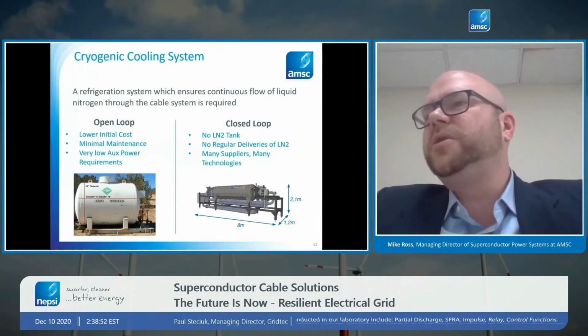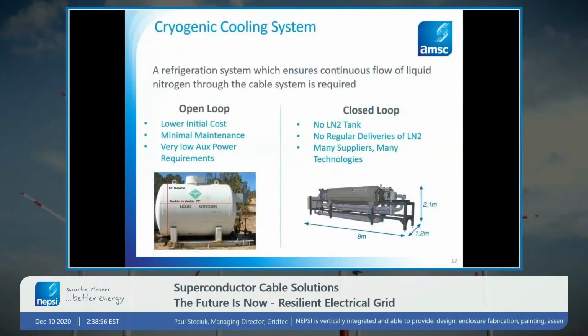Cooling systems are another really important part of these projects. So we talked a little bit about how we have to keep the cables cold. So there's two main technologies. There's open loop cooling systems and closed loop cooling systems. Open loop is usually more attractive to our industrial customers. And basically what you have is a big tank. You rent that tank from a supplier like Airgas or Praxair or Linde or someone like that. And they come along and keep the tank full of liquid nitrogen. And then we consume that liquid nitrogen to keep the cable cold. So we draw the liquid nitrogen out of the tank. We use that to cool our cable. And then the supplier of the liquid nitrogen periodically comes around and fills that tank back up.